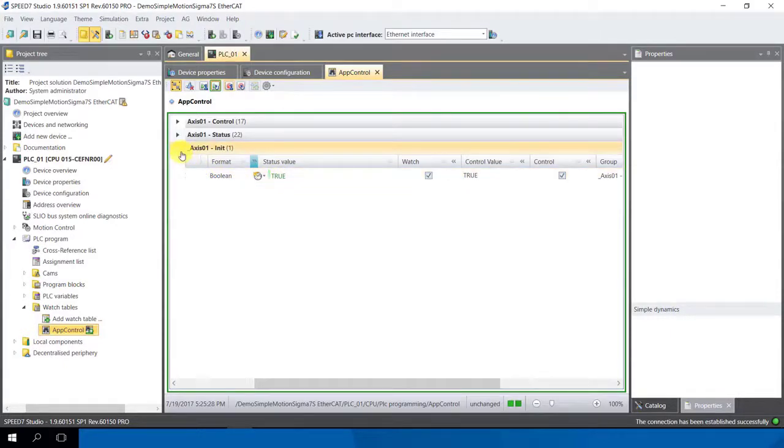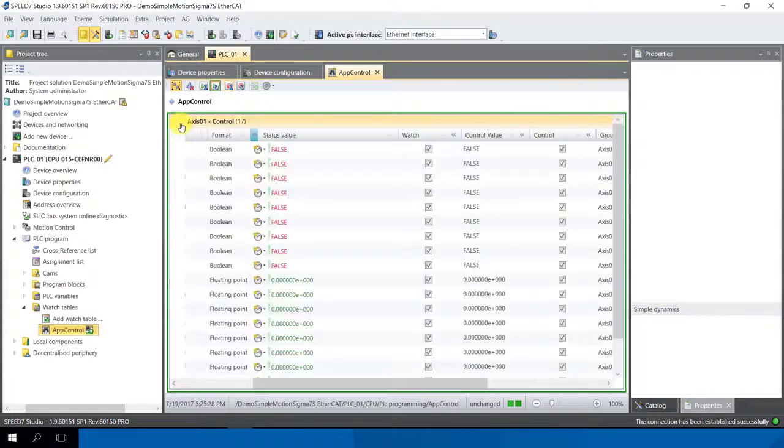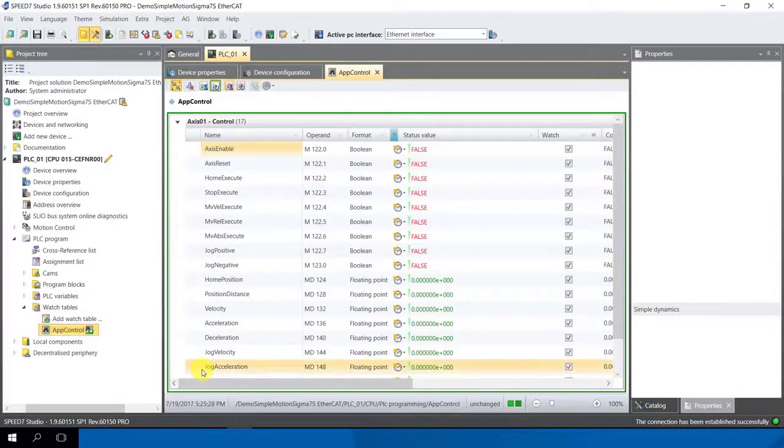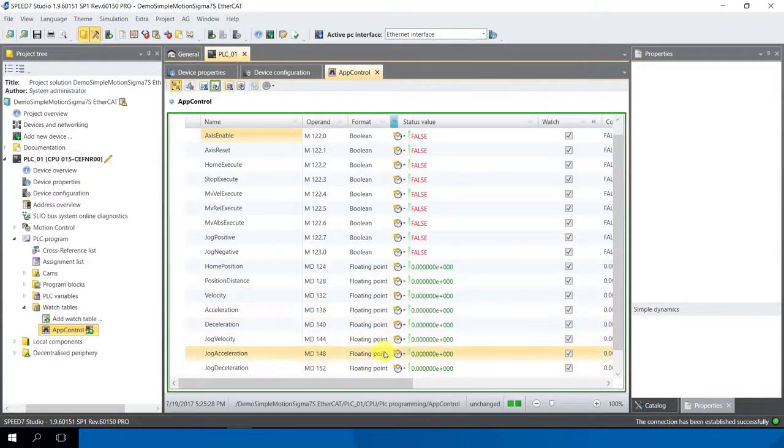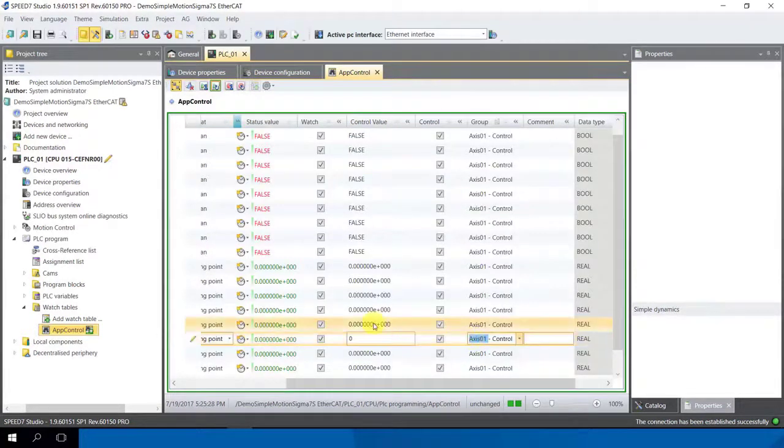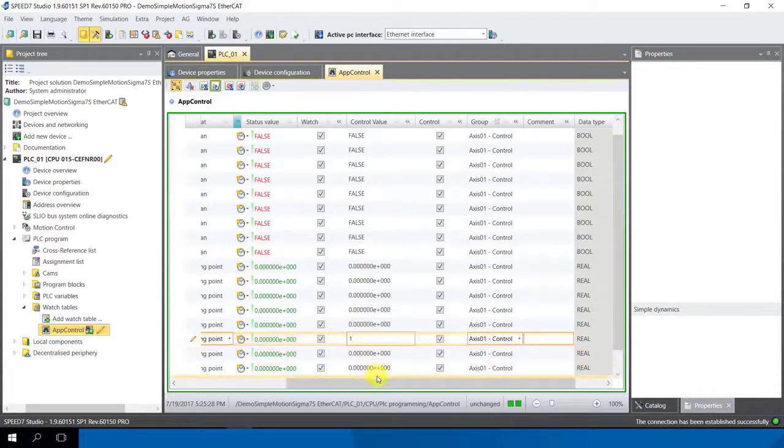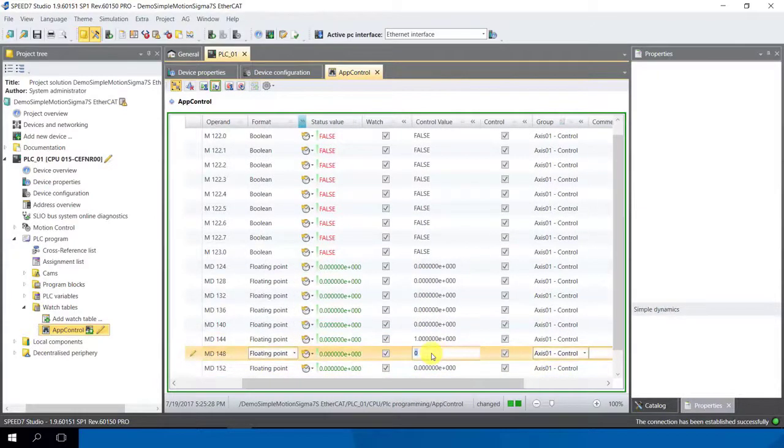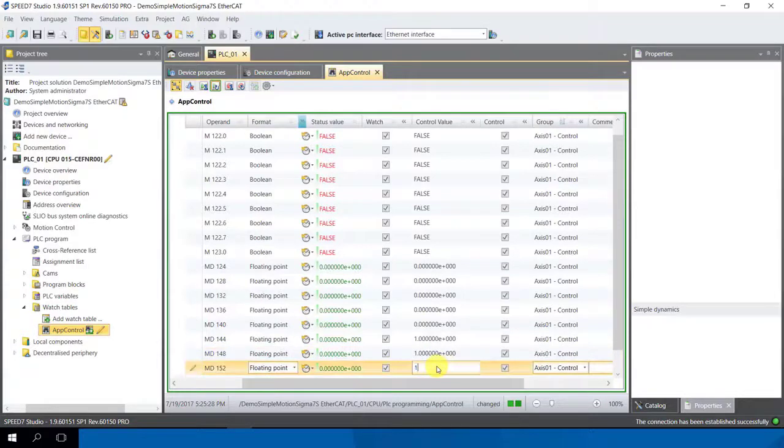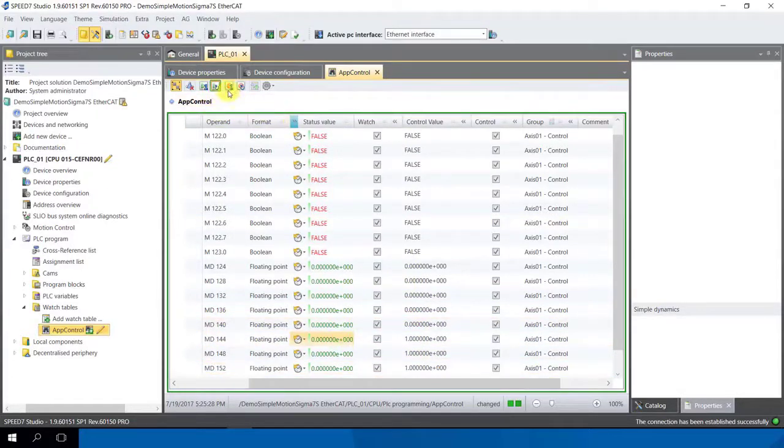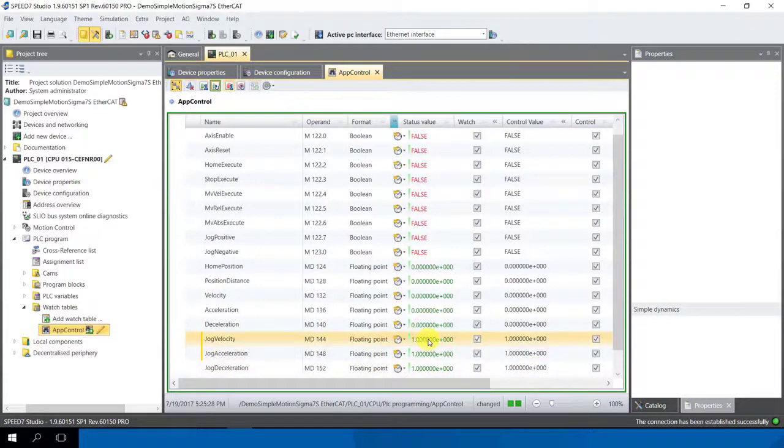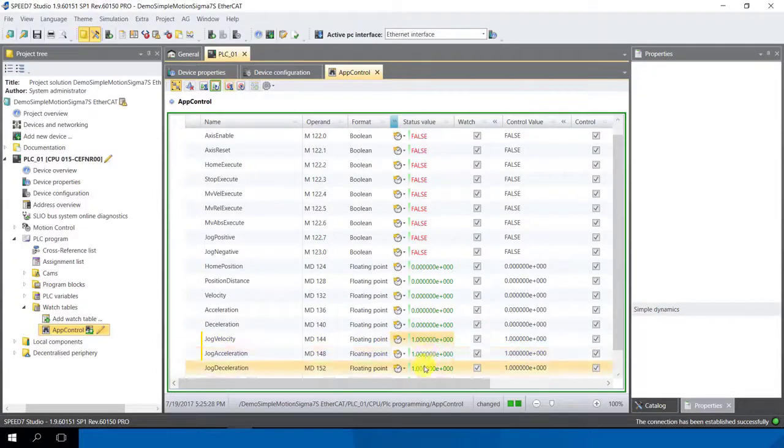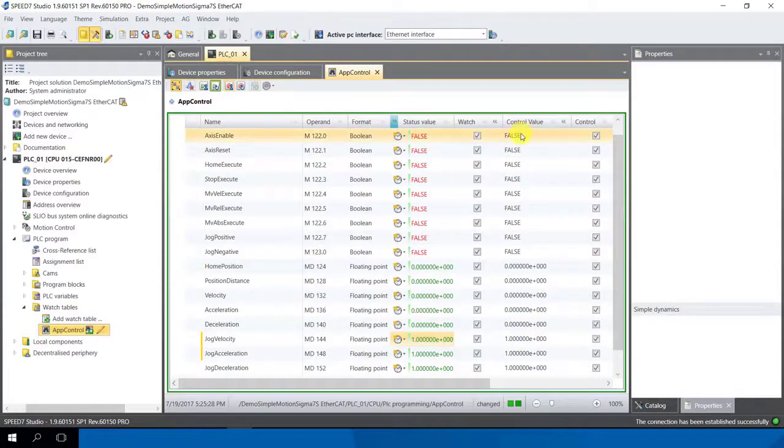We can close this group with init. The next one is the control. Here the first time we need also the settings from the velocity, the acceleration, deceleration, from the jog velocity and the normal velocity. We use here the jog velocity, I change it here to one rotation with acceleration with one second and the deceleration also with one second. I can control these three values here with the button control and you see here automatically my jog velocity is one rotation with acceleration with one second and the deceleration also with one second.